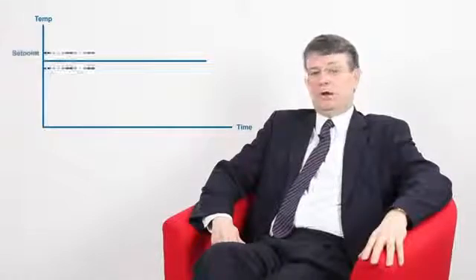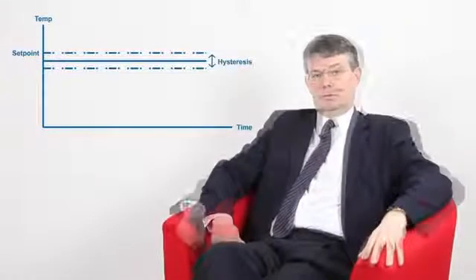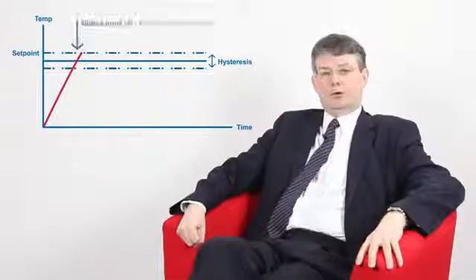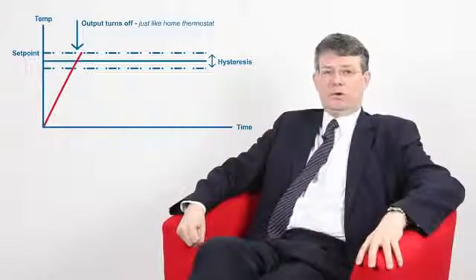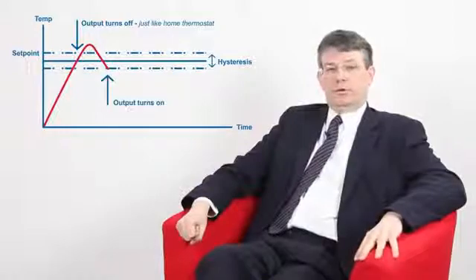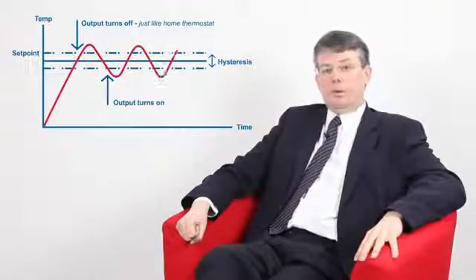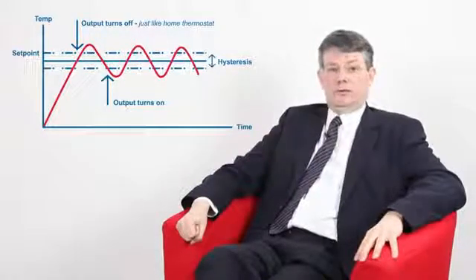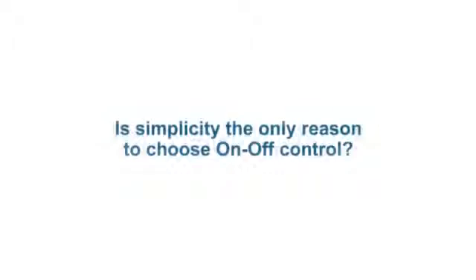We've seen that proportional control will give better stability in the process, so you might wonder why anyone would ever use on-off control. A proportional controller must always be tuned to the process and this can be a little bit daunting for users. If the process doesn't require a high level of stability, the simplicity of on-off control can sometimes be attractive. Unlike proportional control, on-off control only has as a maximum one parameter to adjust. This is the on-off differential.